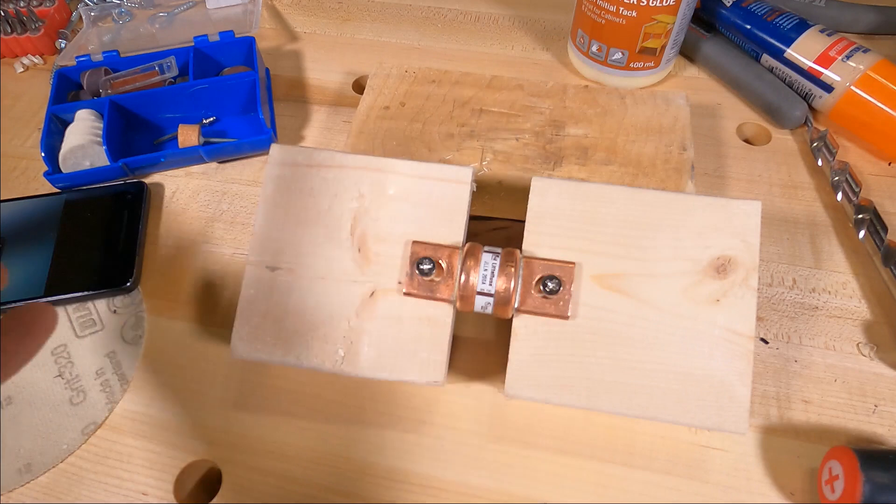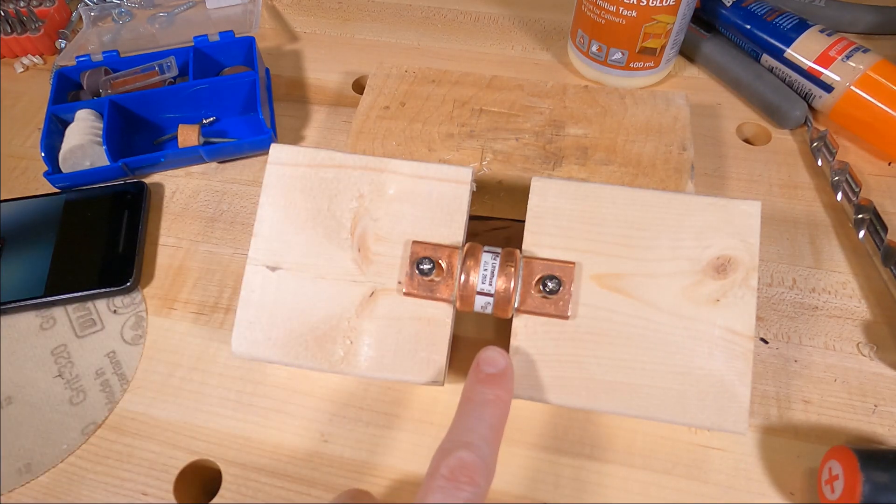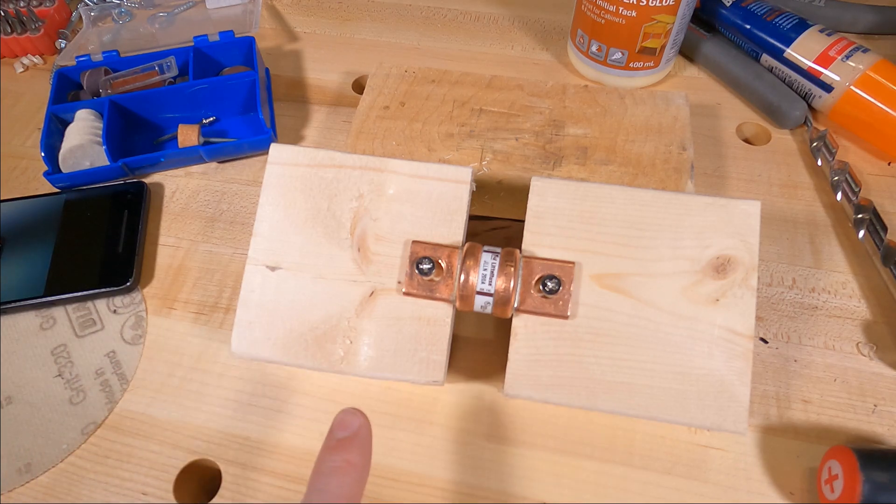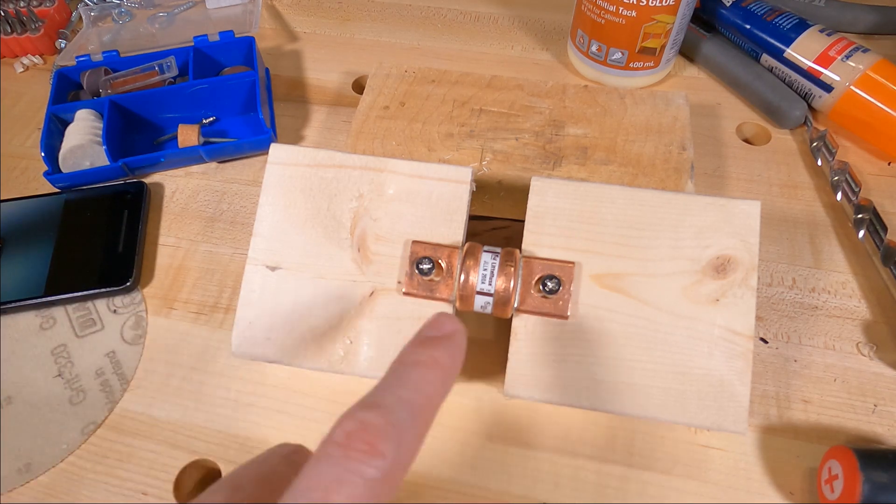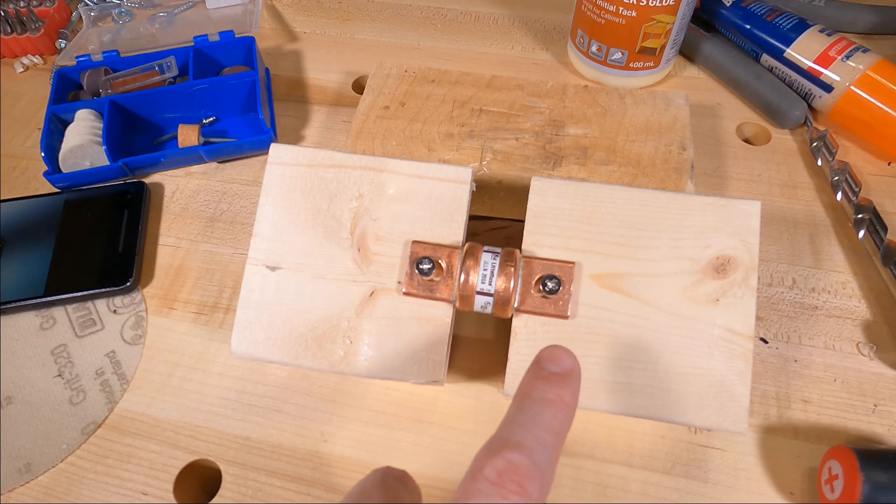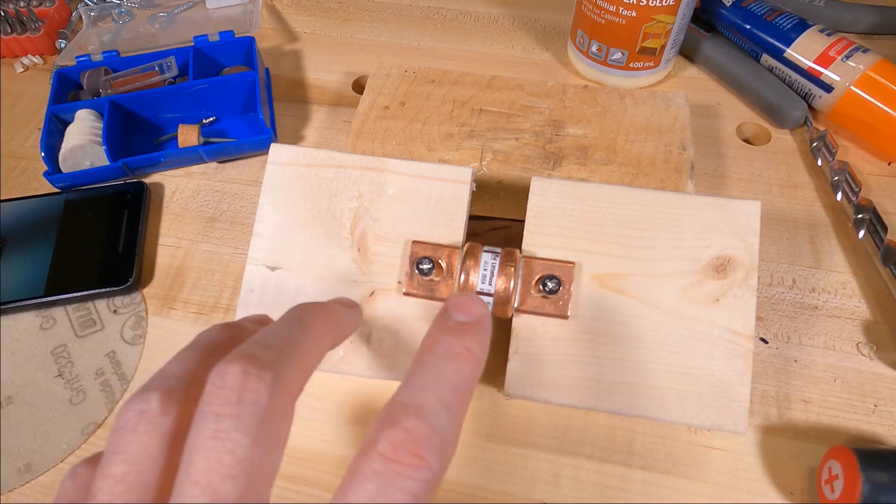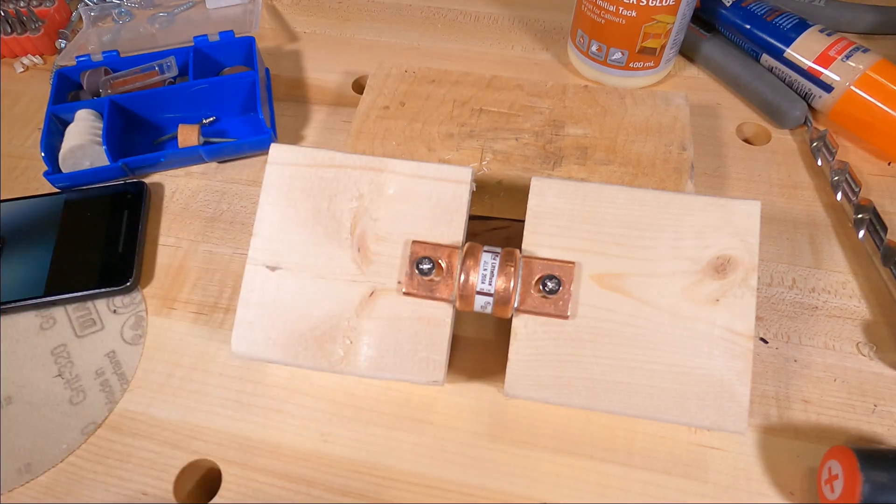This is, as I mentioned in previous videos, filled with silica sand so that if the metal strip that carries the current ruptures, as it did, to prevent the electricity from continuing to flow just because it's arcing over such a short gap, they have sand that quenches the arc. So I thought it'd be fun to rip it open.